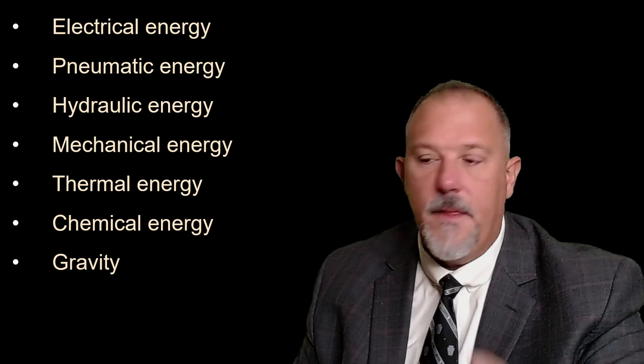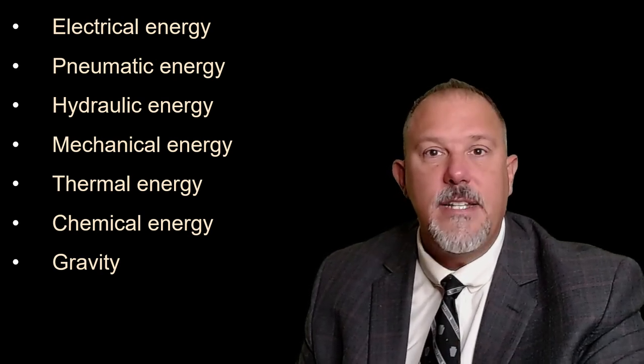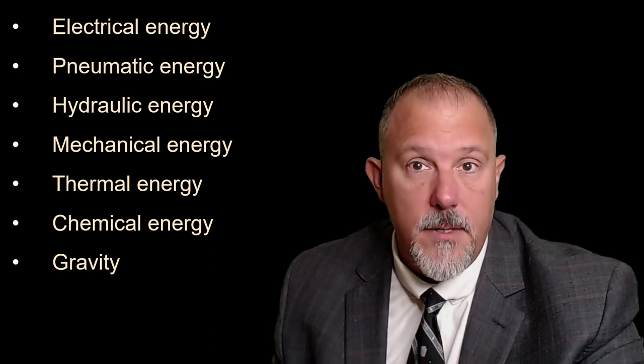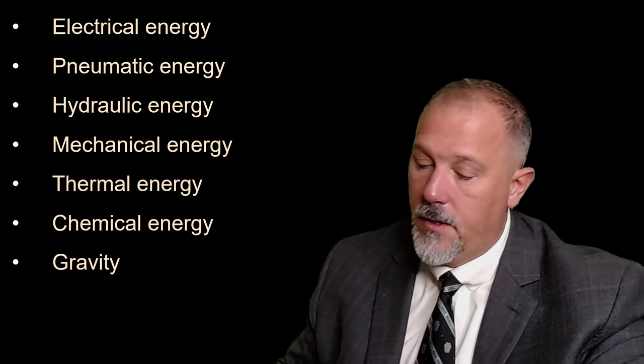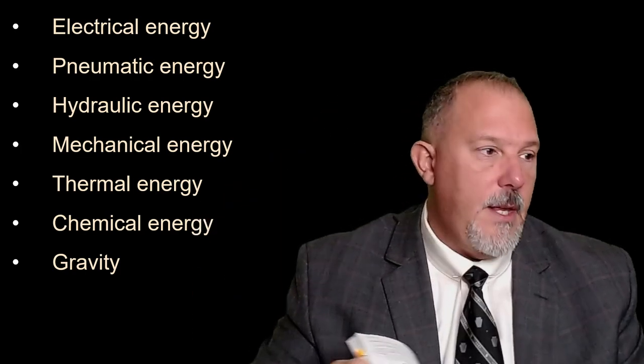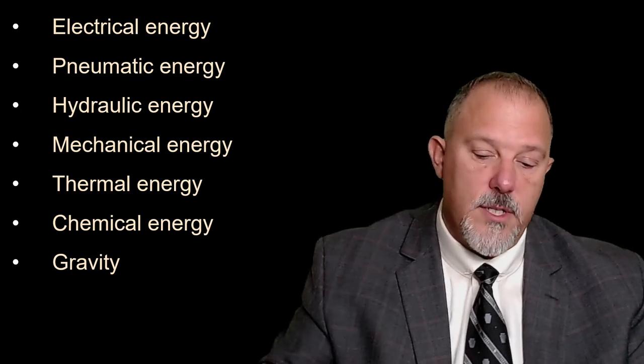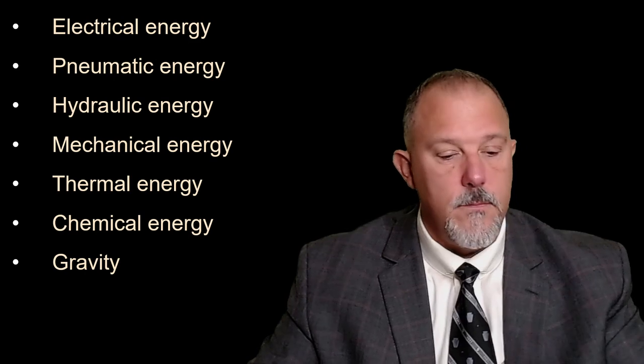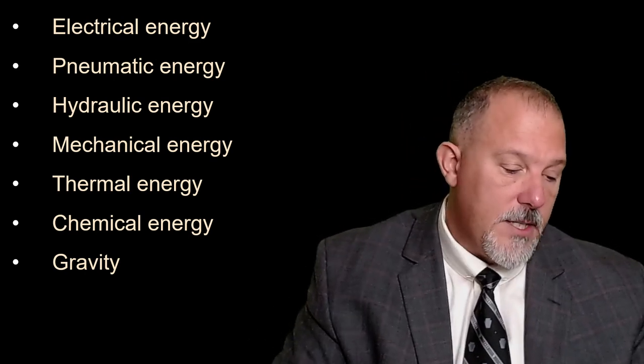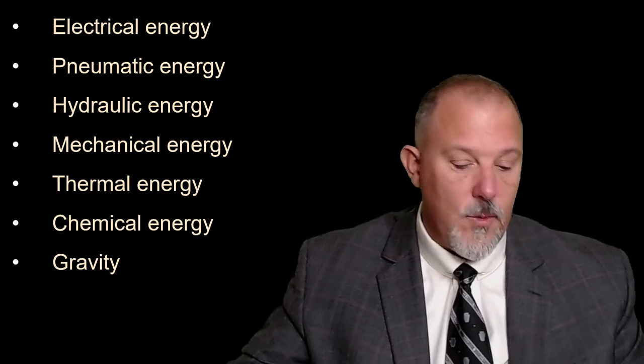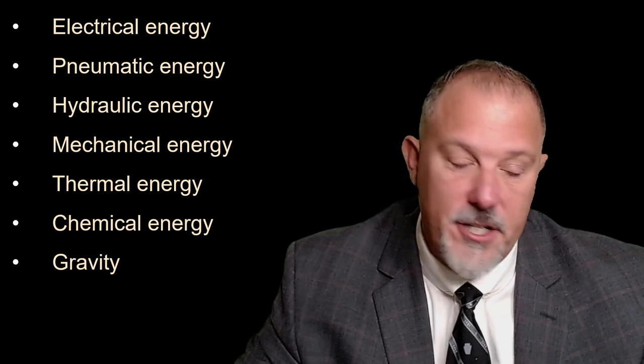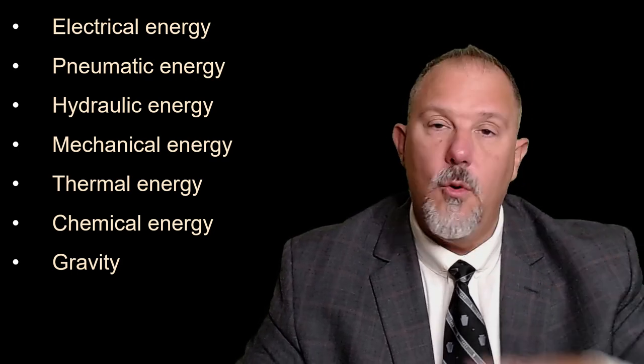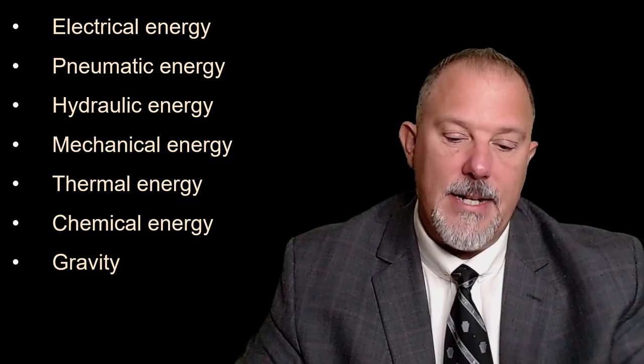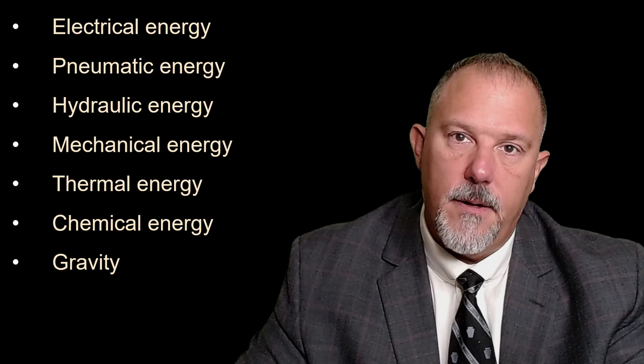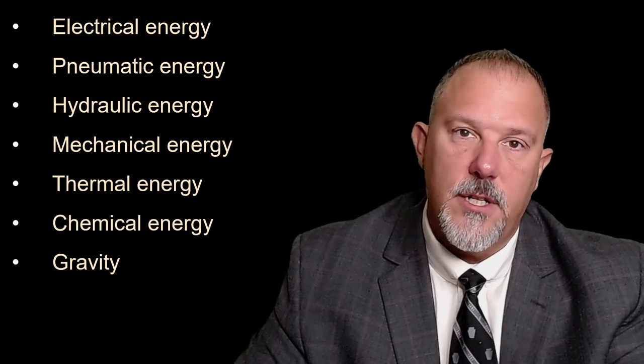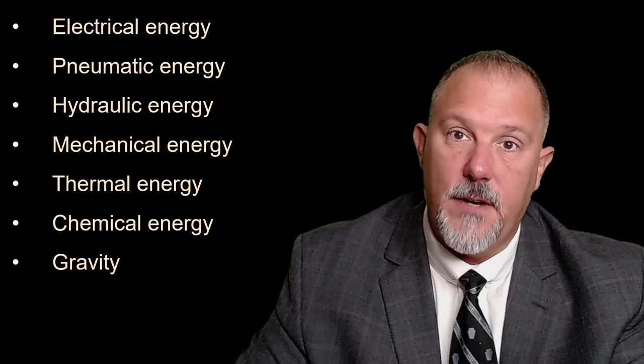And we have to understand that every piece of equipment offers a different perspective. Every system is going to offer a different perspective. If you just look at 70E, and lockout tagout, remember where lockout tagout was? I know you're going to say, Tom, that was in Article 120, because 120 is titled Establishing an Electrically Safe Work Condition. And you look at the whole process of lockout tagout procedures and identifying the sources of energy, and understanding that your system might present different hazards than other systems would.